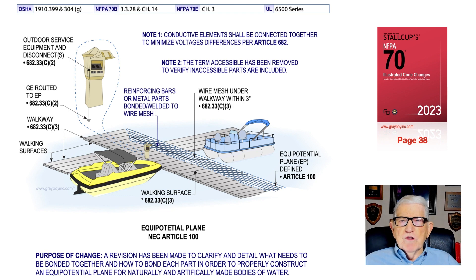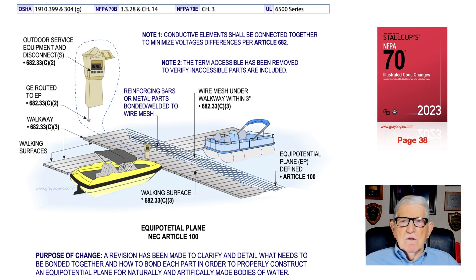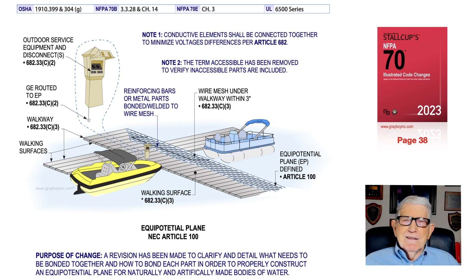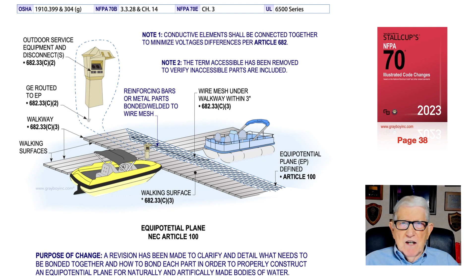In Note 2, the term 'accessible' has been removed from the 2023 edition — it's no longer there as it was in 2020. Reinforcing bars, metals, welded wire mesh — all should be bonded in whether accessible or not, where you naturally have means to access it. Everything shown in blue in the illustration pertains to the change; black print is additional information. The main purpose of this change is that they deleted 'accessible' and said all steel, mesh, and rebar should be bonded together.